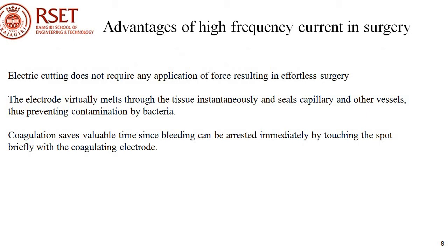The use of high frequency current offers a number of advantages. Electric cutting does not require any application of force, resulting in effortless surgery. The electrode virtually melts through the tissue instantaneously and seals capillary and other vessels, thus preventing contamination by bacteria. Coagulation saves valuable time since bleeding can be arrested immediately by touching the spot briefly with the coagulating electrode.